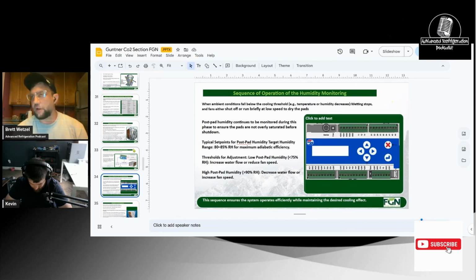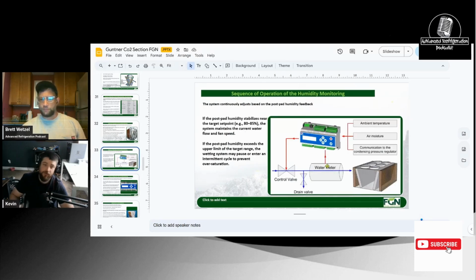So I was trying to figure out how to optimize that, and you gotta talk to Will and I, because I had a theory about it. You don't want to under wet the pads where you're only utilizing just the top end of the pads. You want to utilize the whole thing, but that's what that flow meter is for, and that's why whenever you start one of these up, call Güntner. I'm not gonna lie though, the last two I've started up, they seem to have fixed their pre-shipping program issues, and the pad wetting is close to spot on.